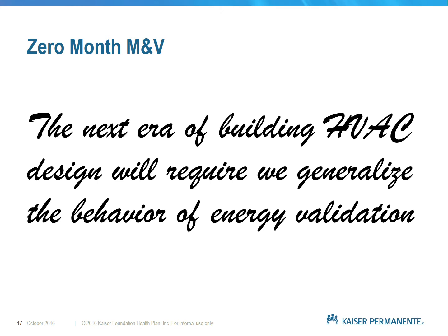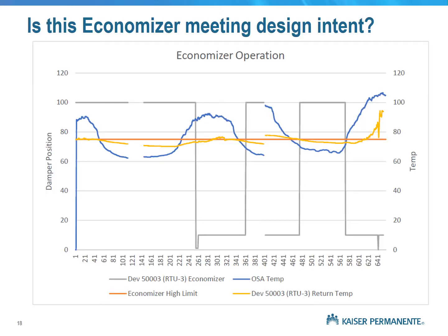I don't know if I mentioned this yet, but on all 14 buildings that I talked about in the early slides, we did full-blown commissioning on all of those projects. So hopefully everyone knows what this is, right? This is a trend log from a building automation system. You have time on the x-axis, and this one happens to be for economizers. So the blue line is outside air temperature, the yellow line is return air temperature, and the gray is the damper position. So if the blue line is below the yellow line, then the damper should be open. And if the blue line is above the yellow line, then, right, hold on, some of this stuff isn't right.